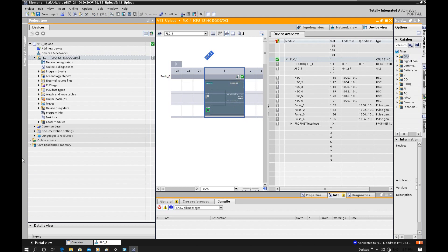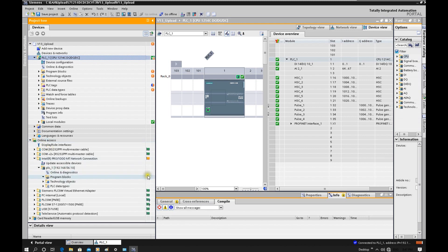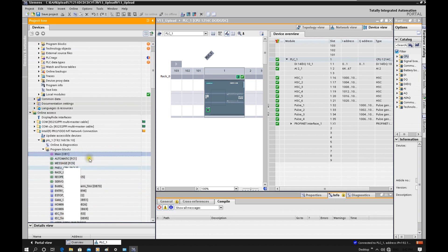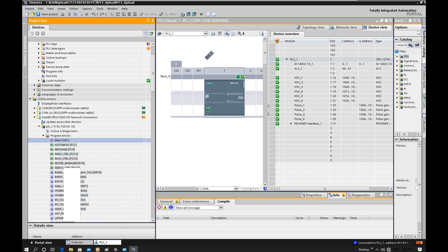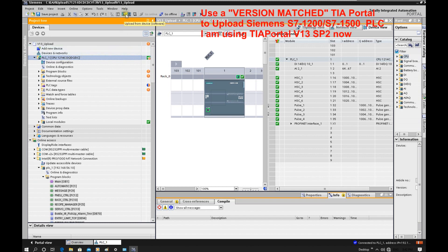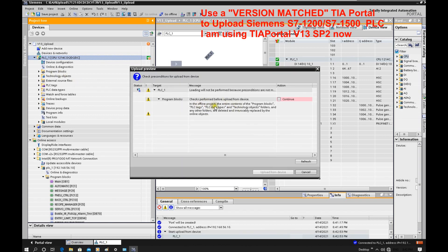Now we are online with the CPU. Let's browse online access. From this online view we can see the program blocks — the controller has multiple functions, function blocks, and DBs. Now let's go to the project here, and we can see that Upload from device is highlighted. Let's click upload. It will show that the offline project will be overridden by the online. That is the upload — so we will proceed.